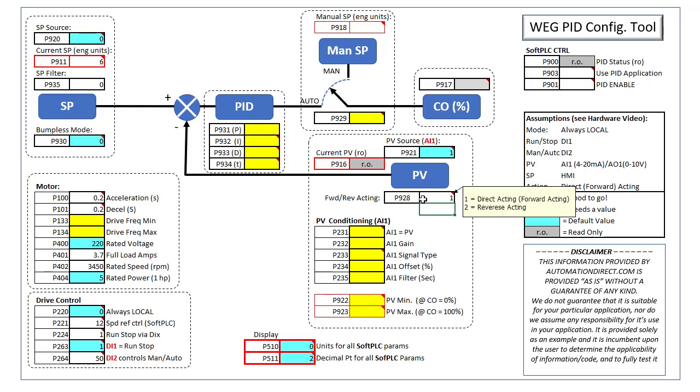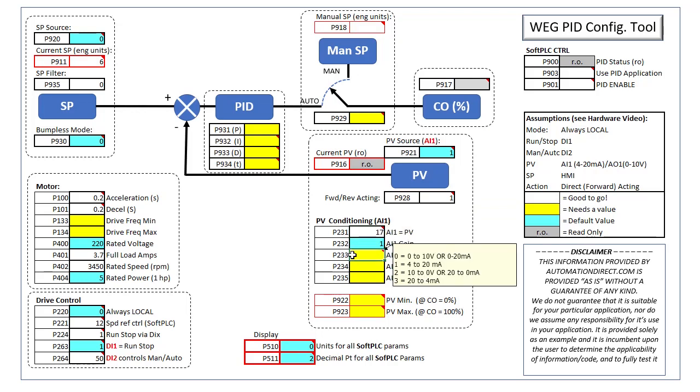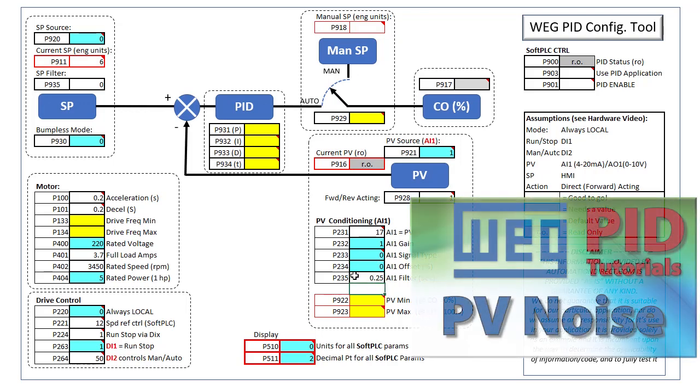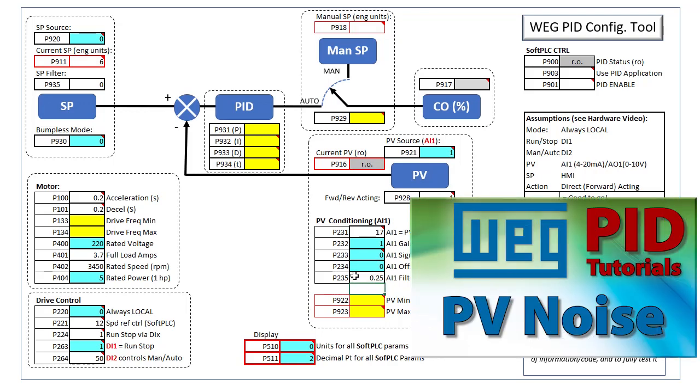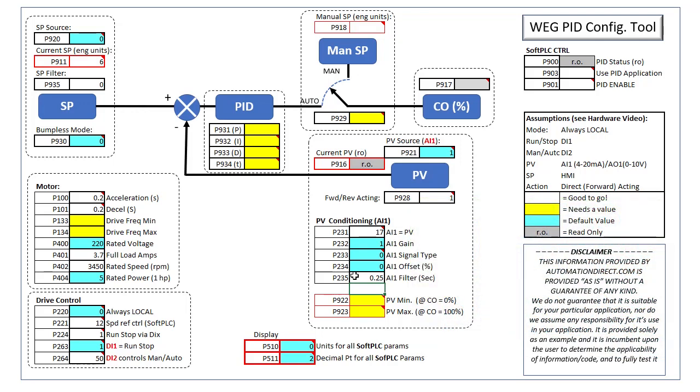Of course we need to set up analog input 1, so we tell analog input 1 it will be used as the process variable and we'll use the default gain, 0 to 10 volt signal, offset and add a little filtering. We have a whole video set aside for techniques you can use to reduce process variable noise. Filtering is just one of those ways.